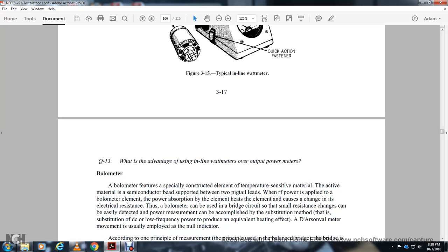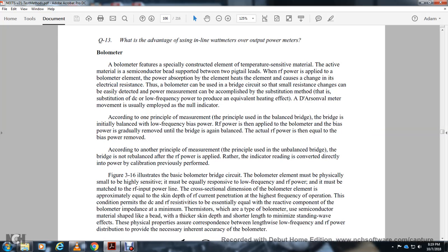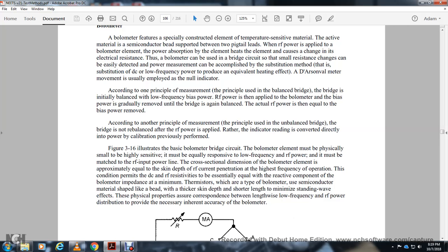Bolometer power meters use a temperature-sensitive element, either a thermistor bead or a barretter, activated by radio frequency power supply. When the bolometer element absorbs RF power, the element heats up and changes its electrical resistance. Small resistance changes are easily measured using a bridge circuit. Power measurement is accomplished by a substitution method: DC low-frequency bias power is applied to provide equivalent heating, with a null indicator employed. The bridge is initially balanced with the bias power, then RF power is applied and the bias power is gradually removed until the bridge is again balanced. The actual RF power equals the removed bias power.